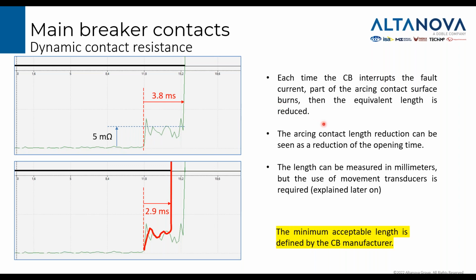So each time the circuit breaker interrupts the fault current, part of the arcing contact surface burns, and the equivalent length is reduced. So we can convert the length in time, assuming that the speed is constant during the operation and constant between operations. Shorter is the time, shorter is the arcing contact. So if I overlap two graphs and I see, for example, a deviation like this, this is clearly a problem in the arcing contact. And the minimum acceptable length is defined by the circuit breaker manufacturers.